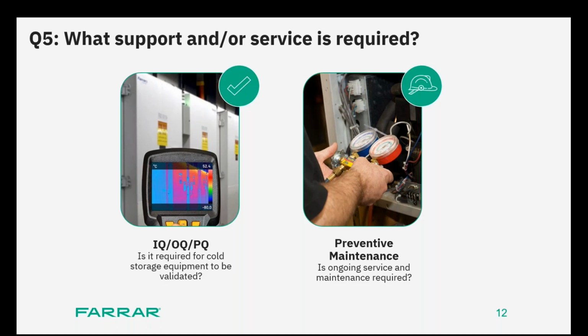So doing PMs and CALs possibly 2 times a year. Some people, every 6 months. Some people are more robust in the sense that they want to do it 4 times a year, every 3 months or every quarter. It's up to you, but it's a good way to get insight. It's a good way to see the future on your equipment.